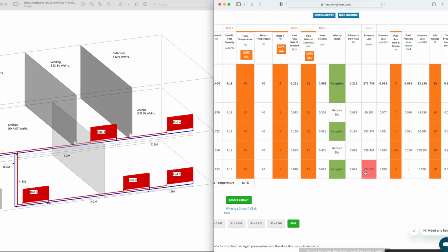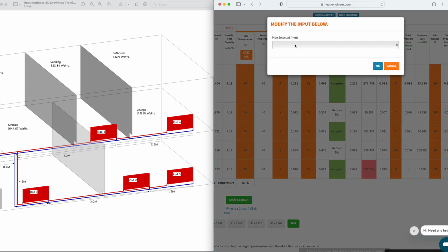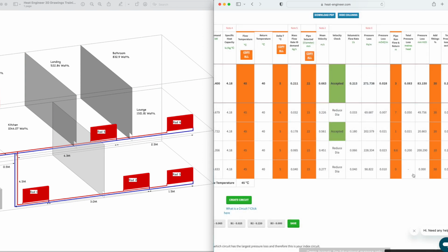One of the smallest pumps you can buy on the market is like a 2040 pump. So 20 mil bore, 40 is 40 kPa or 40,000 pascals. So you think that's one of the smallest that you can get. But because that's 2.5 meters from that point to there, you'd have to double it up so it becomes 5. So it'd be 772 times 5, plus your one change of direction, which is 10%. So I'm not going to go with that. I think we're going to change that, and we're going to put it in as 15 mil, as was stated.